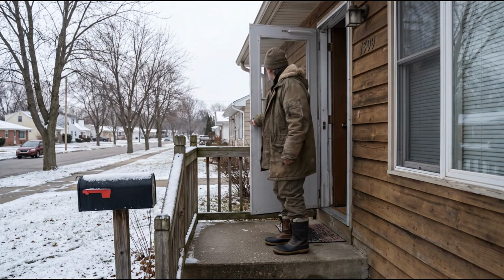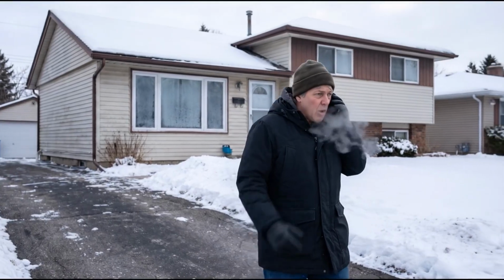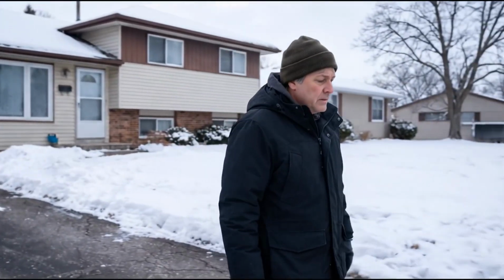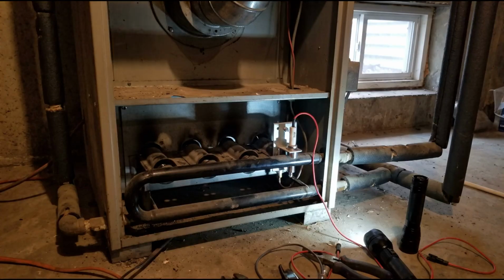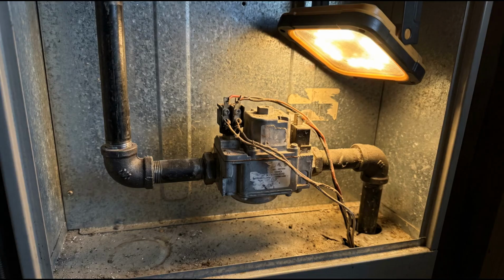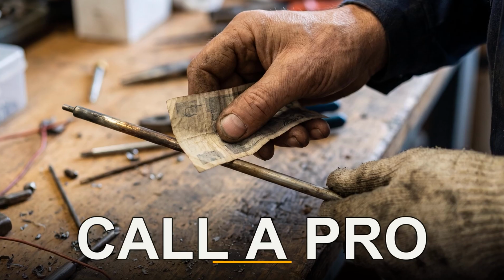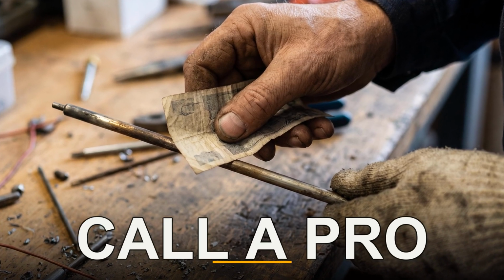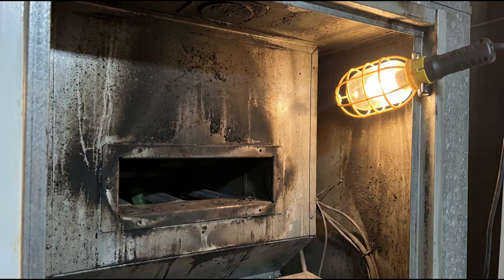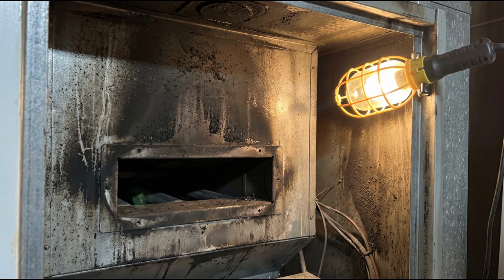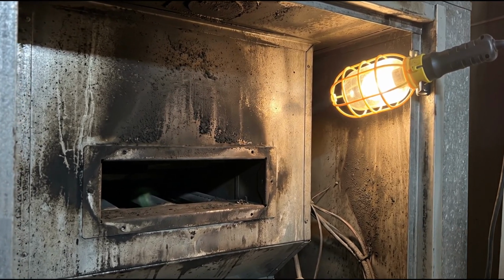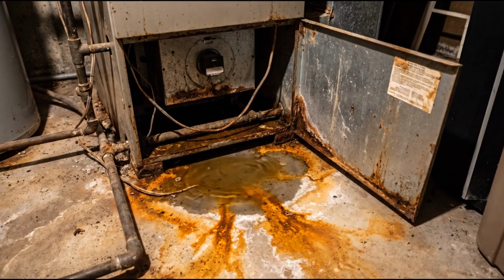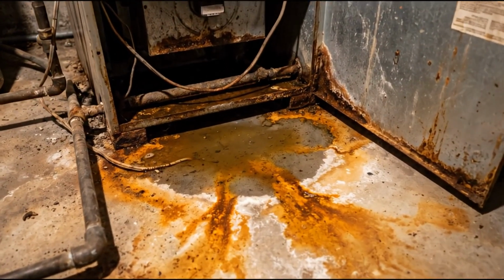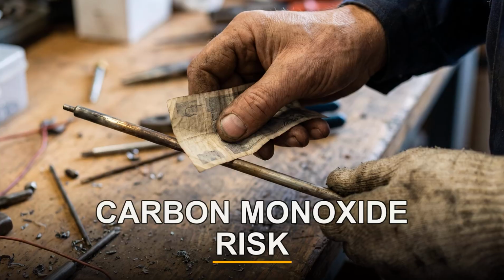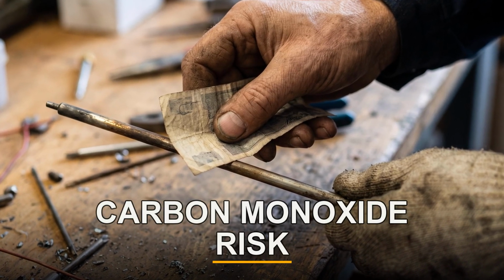Second, if you replace the igniter, it tests good, and the furnace still will not light. Do not start throwing parts at it. Gas valves and control boards are real money, and diagnosing them is genuinely a trade skill. Third, if there is soot around the burner box, rust flakes raining down inside the cabinet, or water where water should not be, that furnace may have a bigger problem, and a cracked heat exchanger is not a maybe, it is a carbon monoxide risk.